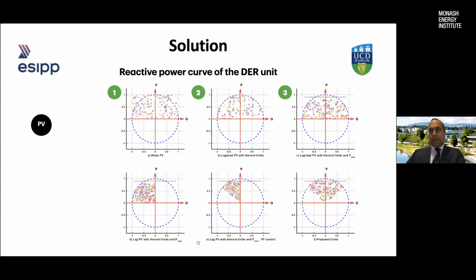So you intentionally reduce the amount of P in order to be able to inject or absorb Q from the grid. Or in case you are only allowed to inject reactive power, then this will be case number 4. And if you have some limitation on the power factor that your PV is allowed to inject into the grid, then you will have extra constraints. And the last graph shows the case where the PV unit is able to both absorb and inject Q, considering all the practical constraints.